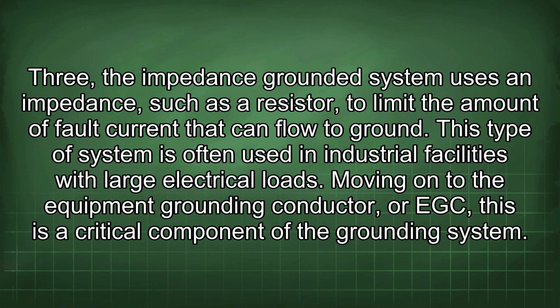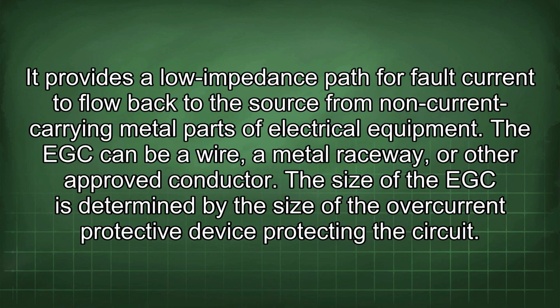Moving on to the equipment grounding conductor, or EGC, this is a critical component of the grounding system. It provides a low impedance path for fault current to flow back to the source from non-current carrying metal parts of electrical equipment. The EGC can be a wire, a metal raceway, or other approved conductor. The size of the EGC is determined by the size of the overcurrent protective device protecting the circuit.